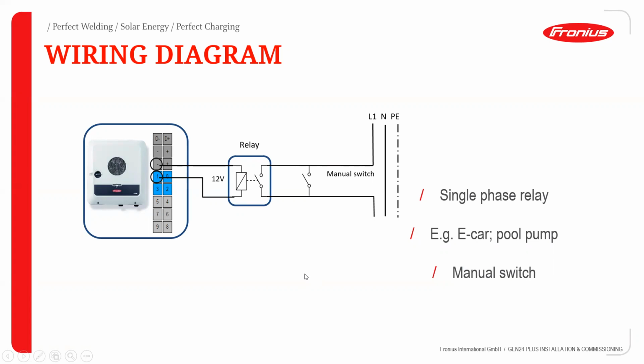To summarize this page, your inverter is programmed via the input-output port. Through this port, we have four programmable input-output ports configured as output ports. Once a condition is reached - for example, if you're generating above, say, 2 or 3 kilowatts depending on your power generation - this serves as a threshold condition to trigger a 12 volt external relay.